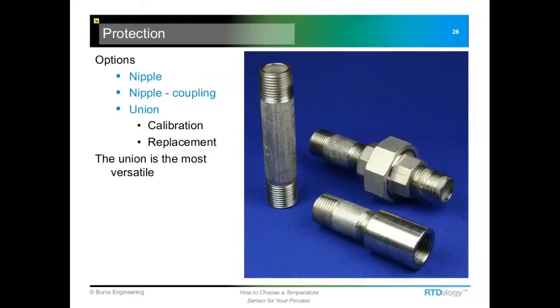Next thing to look at is the extension between the thermowell and the connection head. One of the more simple ones is just a straight pipe nipple. Some of the probes will require a coupling because the probe will have a male thread on it versus just going from the female threads on a well to female on a connection head. The one that I like the best is the one that includes a pipe union. It makes removing and installing the sensor much easier, in that you can orientate the connection head conduit connection any direction that you need just by loosening that union, and you can just rotate it easily and then tighten it up to lock it in place.